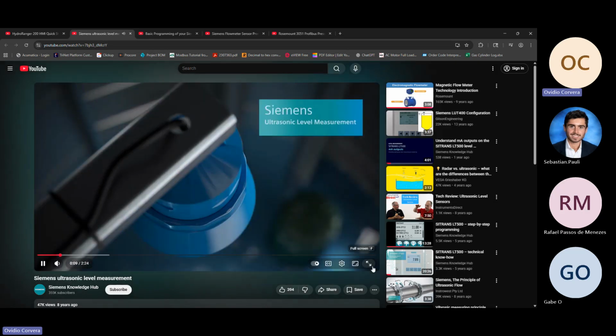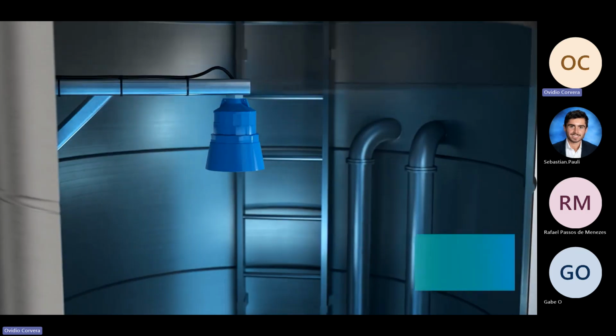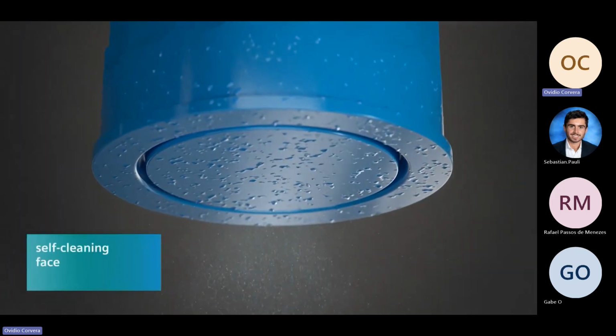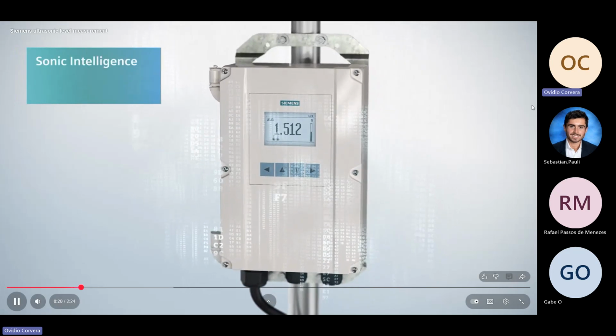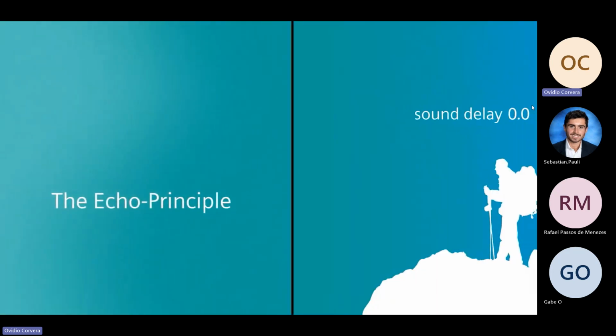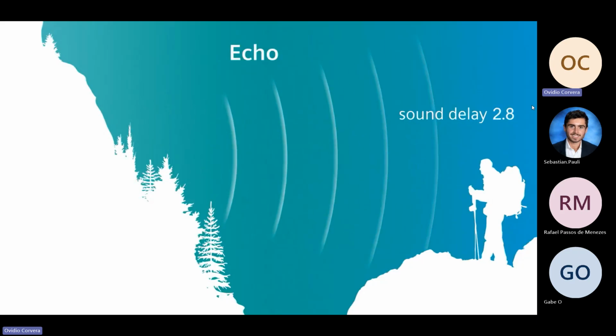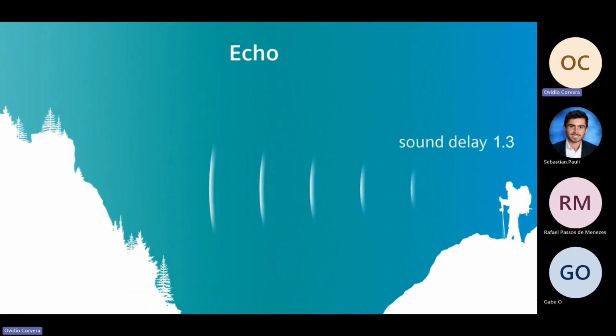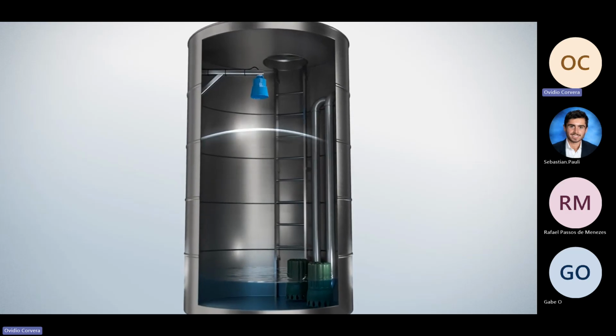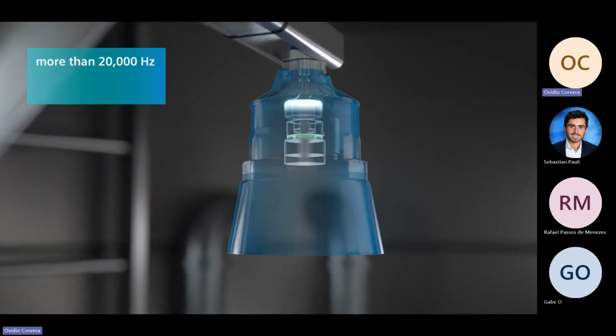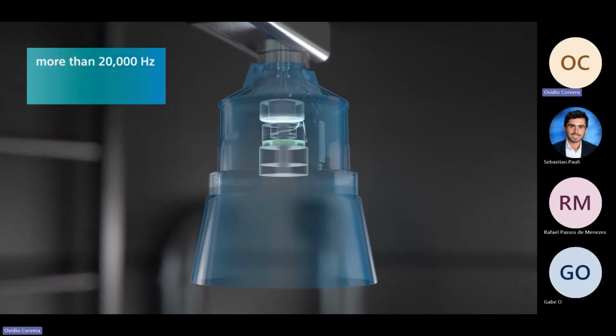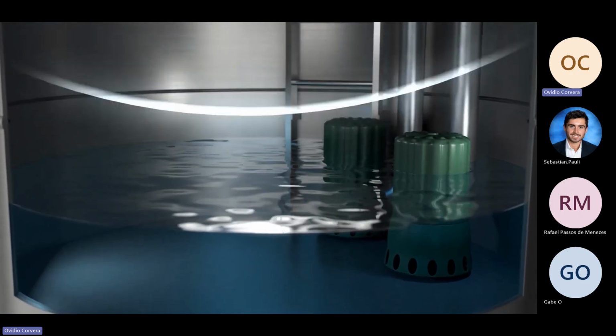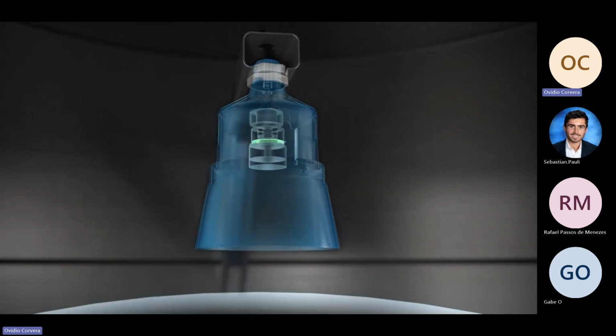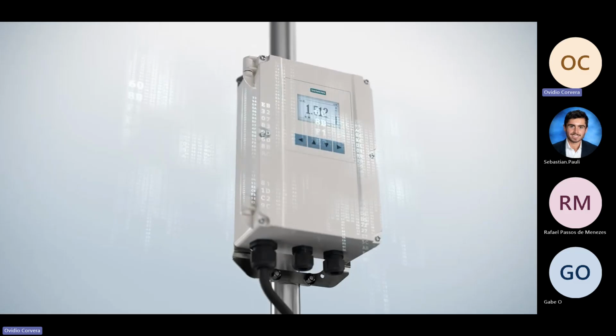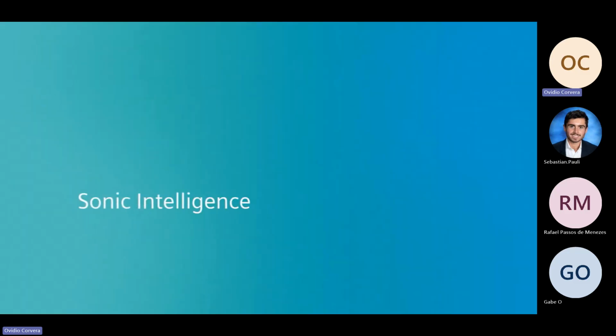Digital signal processing, advanced algorithms. Siemens ultrasonic level measurement provides superior performance, unmatched reliability, and supreme cost-effectiveness. We are surrounded by sound. The time delay between sending sound and hearing the sound is commonly perceived as an echo. Ultrasonic level measurement takes advantage of this effect. A piezoelectric crystal inside the transducer converts an electrical signal into ultrasonic sound. The sound reflects from a surface and travels back to the transducer, where it is converted into an electrical pulse. A digital signal processor analyzes the time delay and calculates the distance.